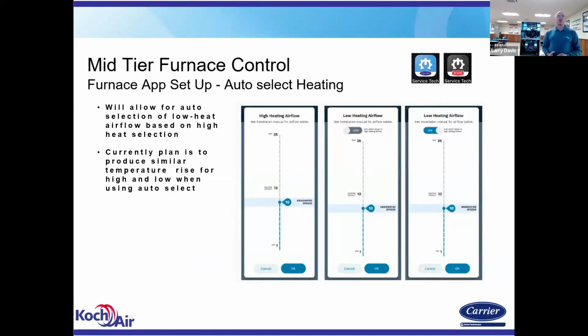Again, the auto select for the heating airflow. You set your high heat airflow based on your temperature rise. Your low heat airflow, you have the option of letting it auto select, or you can manually do it. Either way. And there at the top right of the slide, you see the emblems for each of the service apps. So earlier on, when I told you to load the service app, if you missed that section, that's the symbol you want to look for in your app store for the Carrier or Bryant Service Tech app.